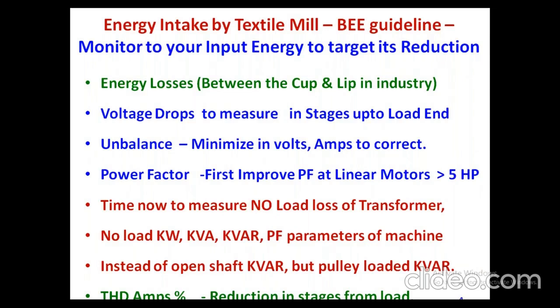Any unbalance in voltage in any of the machines. This is why we always insist, as an energy auditor, on each and every machine, let us say the ring frames, which consume almost 50% of the consumption of the textile mill. Each and every ring frame is supposed to have a basic voltmeter and ammeter, apart from the kWh meter, kilowatt, kVA and power factor.